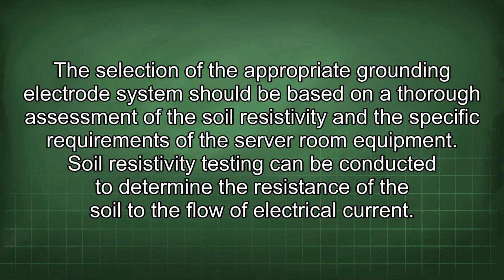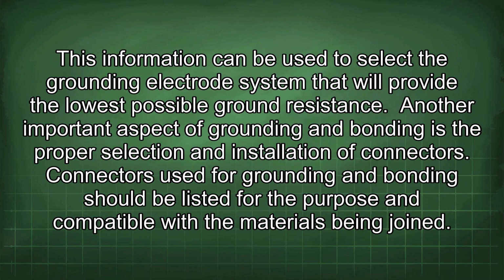Soil resistivity testing can be conducted to determine the resistance of the soil to the flow of electrical current. This information can be used to select the grounding electrode system that will provide the lowest possible ground resistance.